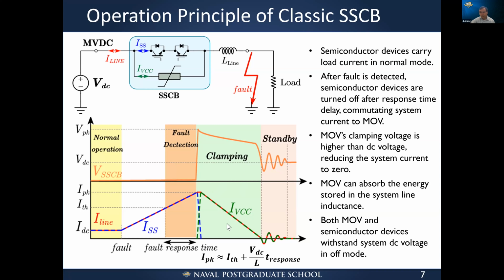After the fault current, the system current, is reduced to 0, the fault is cleared. Then both the devices and the MOV will be in standby mode, and we need to withstand the full DC voltage. That's the basic operating principle. And the peak current here can pretty much be estimated as the ITH threshold current plus the di/dt, VDC over L, times the response delay.